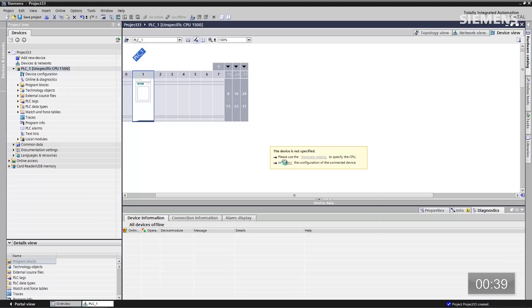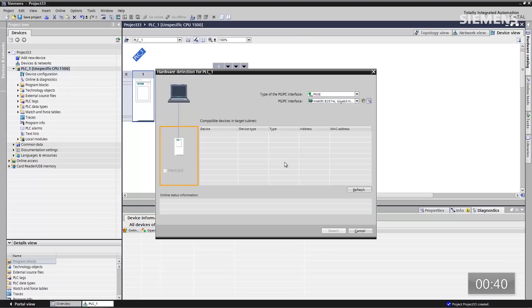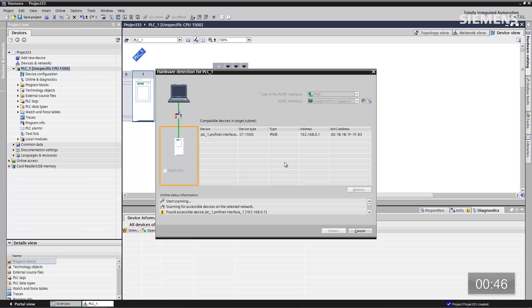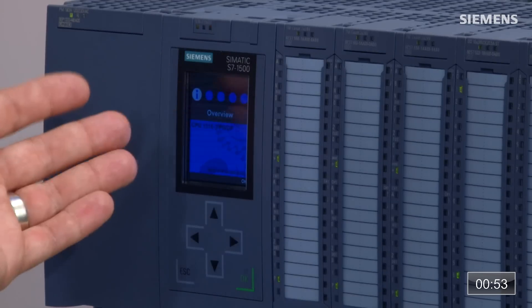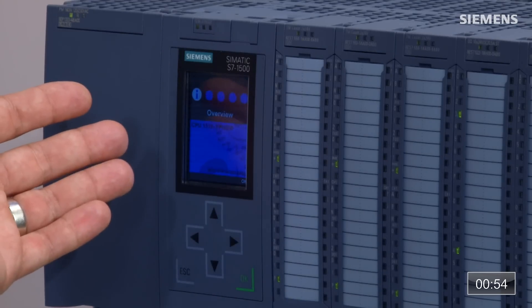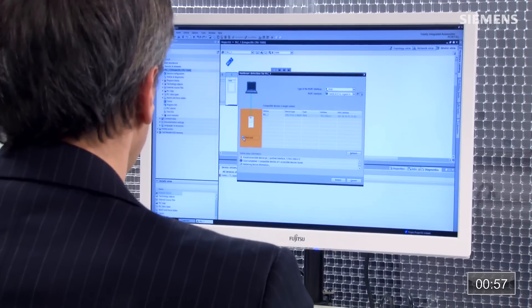Once it's done, I have the option of clicking on a Detect button here. At this point it's going to go out and search for IP addresses and device names of 1500 CPUs. It has found one. On the left side of this dialog box, we have the ability to click on Flash LEDs — you can see that we are flashing LEDs in this particular rack. So this is the correct choice.